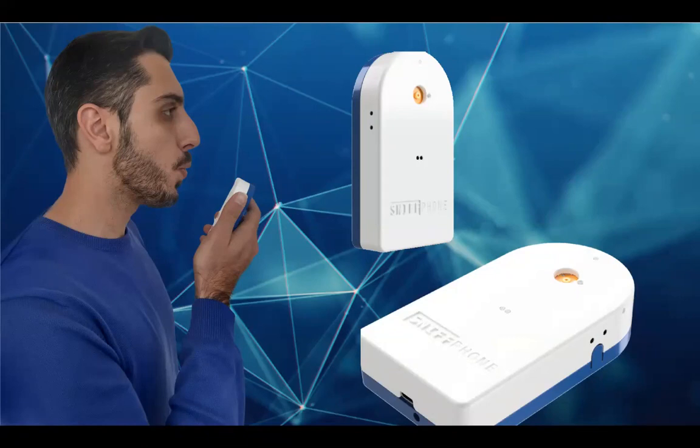And this device allows capturing the breath from a distance of 1 to 2 centimeters without intervention of any contamination from the environment. The device will pump the breath through a micro pump into a microfluidics, which hosts the sensors where the reaction will be done. And from there, this device is connected through ICT technologies, and we get the results as I explained earlier. And the most important part of this device actually is the artificial intelligence or the machine learning, because again, this device has to be trained.